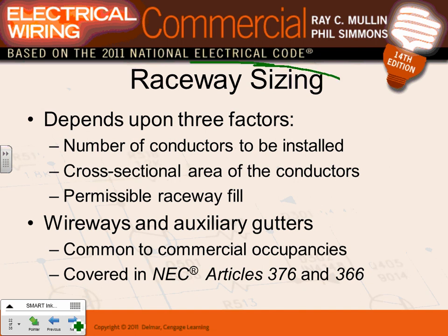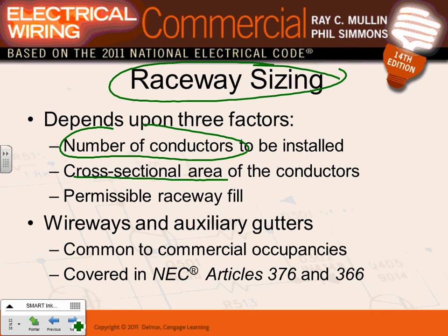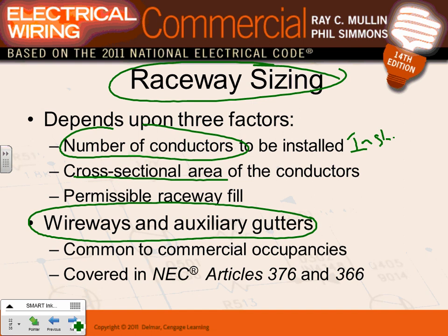Wireways and gutters: in chapter three there are close to 40 to 50 wiring methods. You're lucky if you use 10 of them in your career. Another common type is wireways and surface-mounted raceways - there are metallic and non-metallic versions. Gutters: if you have a panel and want to expand it for bending conductors, you add a gutter box next to it to give bending space. Wireways are limited to 30 feet; surface-mounted raceways have no length limit. Schools are notorious for using surface raceways.